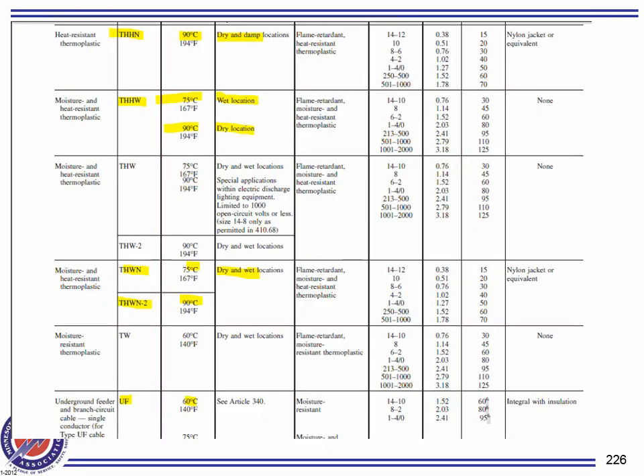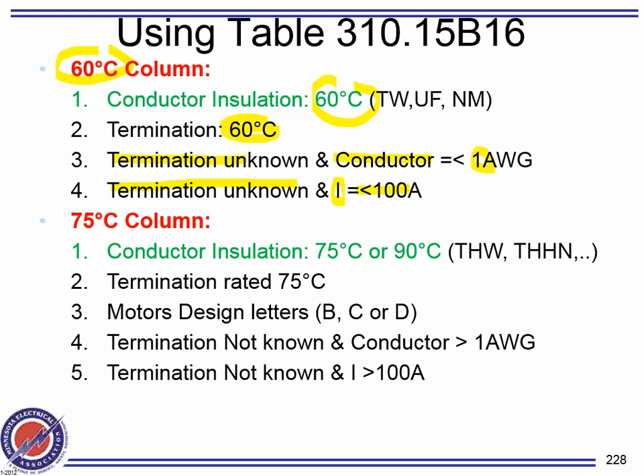All right, now let's go to 75, gentlemen. 75. Now, to use the 75, the single most important thing is that your conductor insulation must be 75 or 90. I can't emphasize that enough. Say you decide you want to use THHN. That's 90. Now you go to the rules. Rule number one. If it says the lugs on the machine are rated for 75, then you go 75. But remember, the insulation first must be 75 to go through these rules.